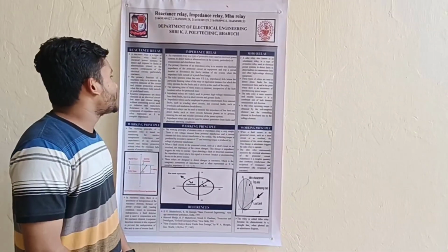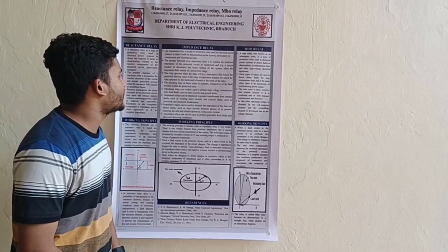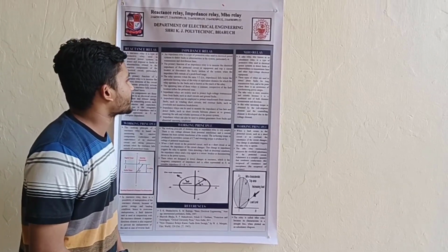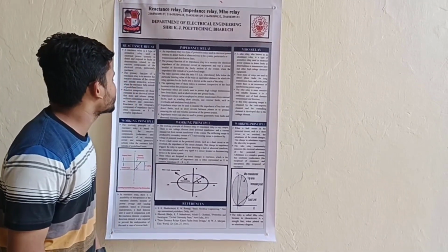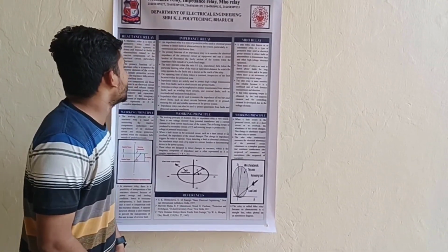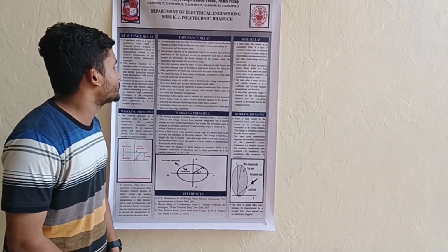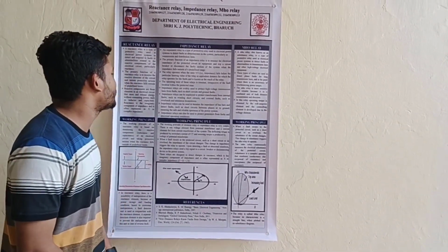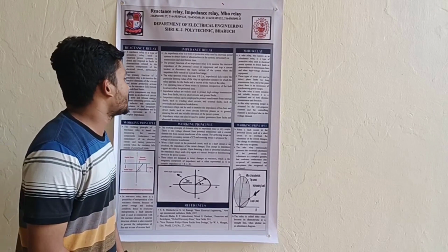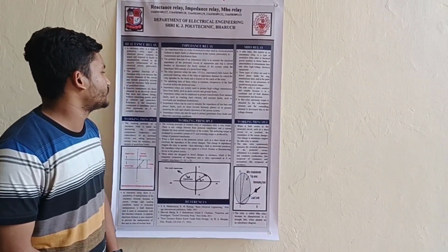The operating time of this relay is independent of the fault location within the protected zone. Impedance relays are widely used to protect high voltage transmission lines from faults such as short circuit and ground fault.